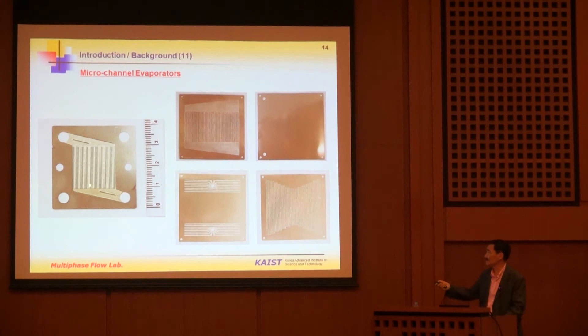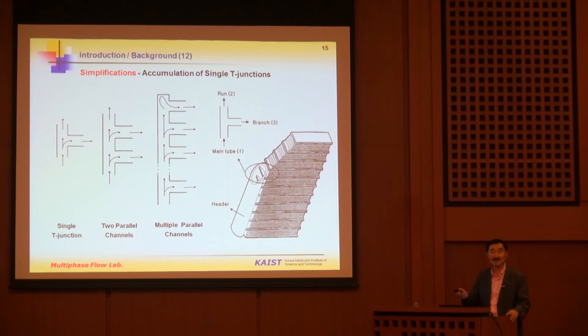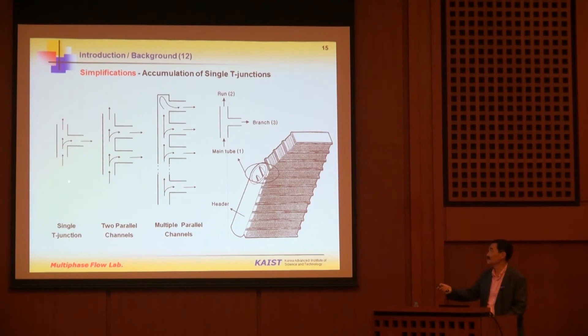For micro-channel designs, you have an inlet header, an outlet header, and channels of several hundreds or tens of microns. Flow maldistribution is quite important here. The header and channel assembly can be considered as an accumulation of single T-junctions — that is the elementary unit. Two-phase mixture comes in, part goes out through the side branch, and the rest continues to the run.